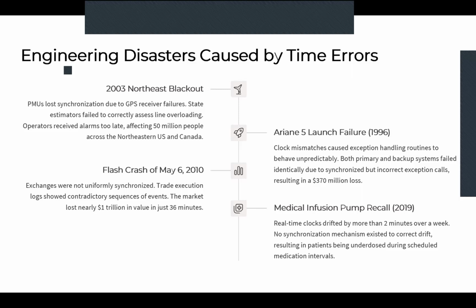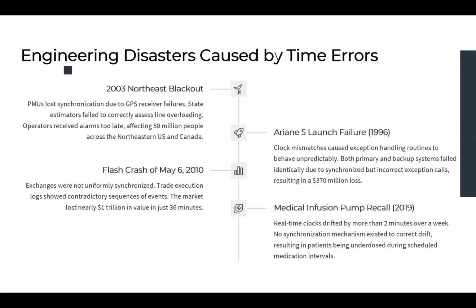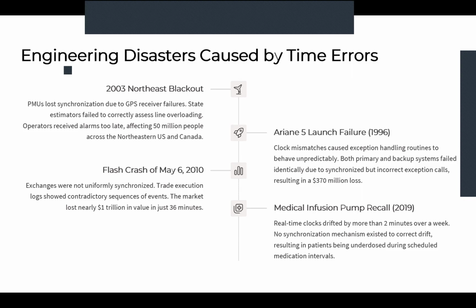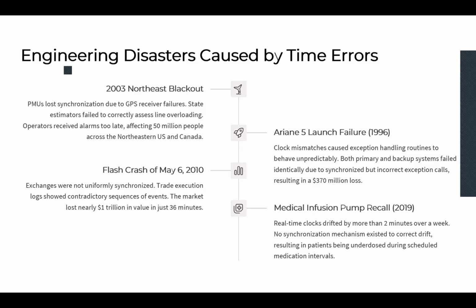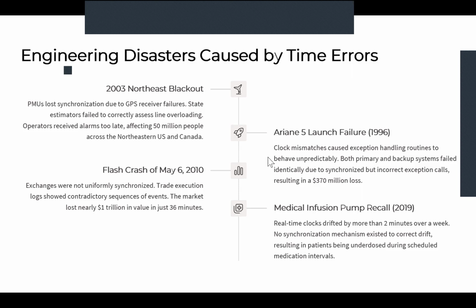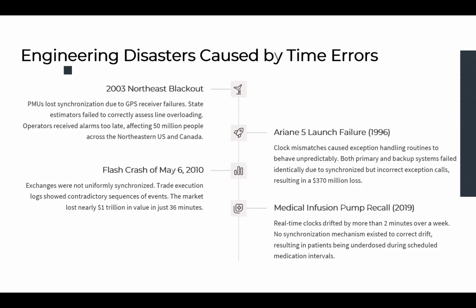Another example is medical infusion pump recalls, where that medical device administered an underdose over time because of the time drift, and it was a massive recall. What happened is that the internal real-time clocks differed by a little bit more than 2 minutes per week. There was no synchronization network mechanism like the NTP or PTP protocols. So the medication scheduling basically became misaligned with the actual patient timing, the prescription that was set for that patient. So you see how important time is in a variety of fields, and how time desynchronization could create a very huge disaster.